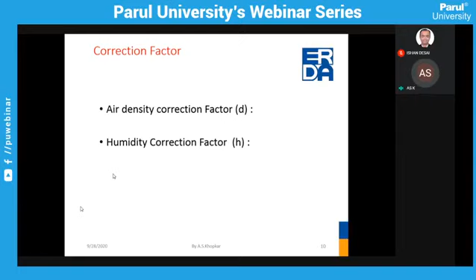There is a very simple method given in the standard. Majority of the standards on high voltage testing techniques give graphs and formulas, and based on that formula we can correct the test voltage. The meaning is that if we have to apply 28 kV, then depending on the atmospheric condition, sometimes we have to apply 29 kV, or sometimes 26 kV or 27 kV. So depending on the atmospheric condition, we have to apply the correction factor on the test voltage, and then do the high voltage testing. Now this high voltage testing may be of any product.